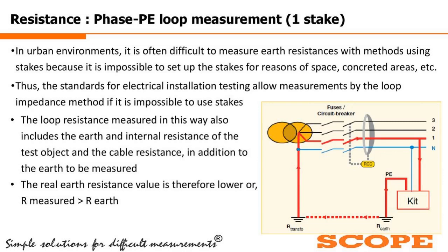Loop resistance measurement is done in the very same way as we measure voltage and current. As we did with the RCD, which has been mentioned over here, you can consider it the same as the earth leakage clamp which we used in the earlier case. So that RCD clamp we will be using. The loop resistance measured in this way also includes the earth and the internal resistance of the test object. Since it is an in-circuit measurement, the resistance of the cables connected, or anything coming in series in the measurement path, all those resistances come into the picture and get added over and above the actual value of the earth resistance.